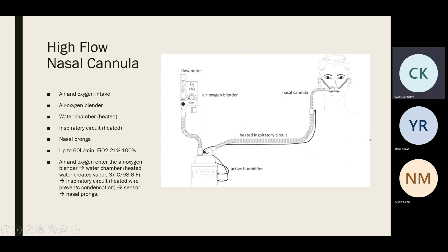Here's a diagram of the high flow nasal cannula system. The main parts are the flow meter, air-oxygen blender, humidifier, heated circuit, and the nasal cannula. What happens is: you have an air intake and oxygen intake, delivered to the air-oxygen blender. This blended oxygen, depending on your flow rate and FiO2 settings, is then delivered to a water chamber.